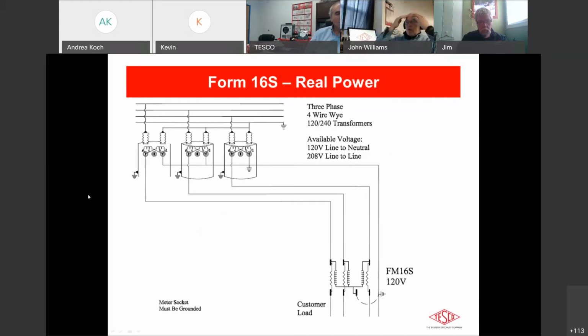Finally, the 16S, as we mentioned before, is the counterpart to the 9S in terms of self-contained applications. Kevin made a good point in terms of the installations in his territory, going more to the CT rated ones because of the ease of testing and safety concerns. But again, this is something that you may want to look at in terms of the cost of installation as well, where if your load is capable of being measured by the 320 class 16S, that might make sense for you, so as to cut down on all the installation and the additional wiring and so forth.